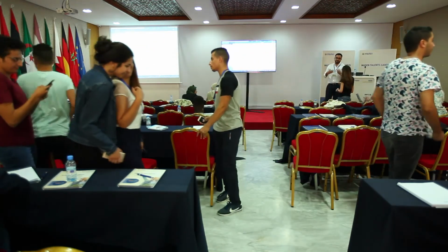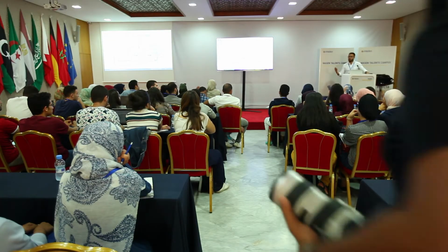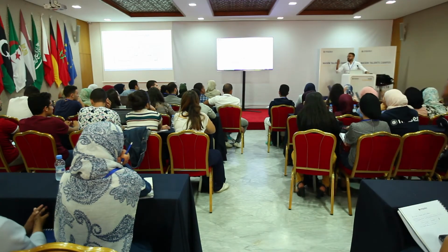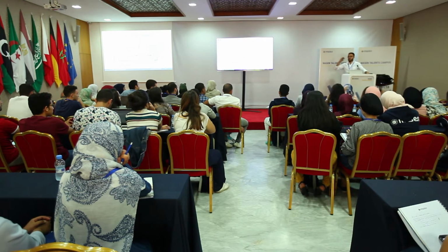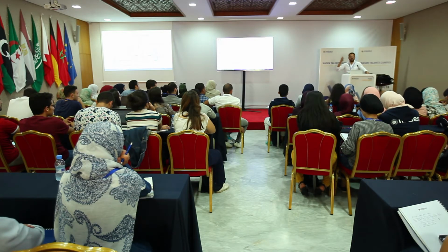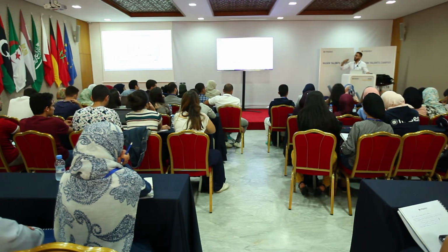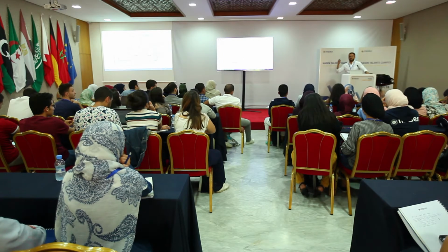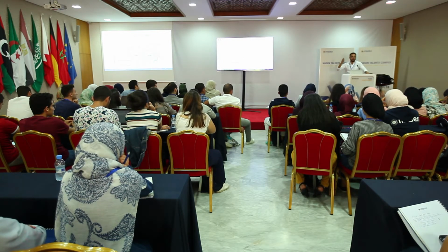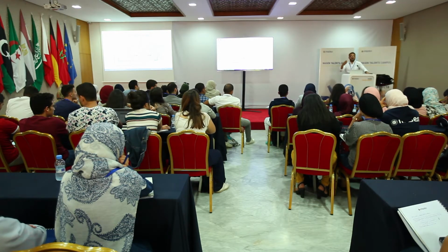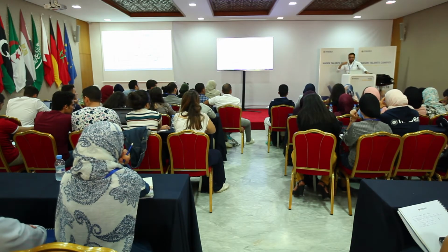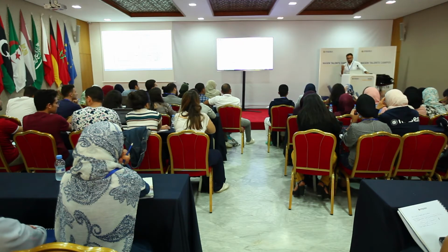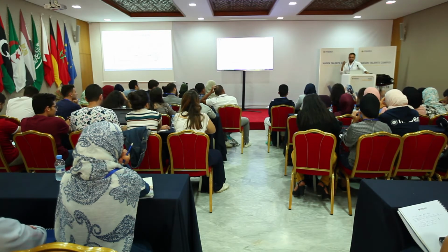So for plant A, for a price like this, with that location, like DNI, maybe the optimizer says the best is a plant with 110 megawatt electric, only 4 hours of storage, a solar multiple of, I don't know, don't look into solar multiple, let's say a mirror area of 1.3 million square meters, tower height, etc. You can look into this. And each of them is a power plant. It's just different. B is a power plant that is almost like a base load plant, 14 hours. So this comes back again to the question of how large should it be? What's the optimum size? Well, it depends. It depends on how I'm paid. It depends on what the market wants. It depends on what the drivers behind this are.